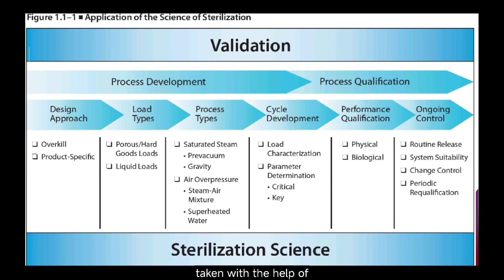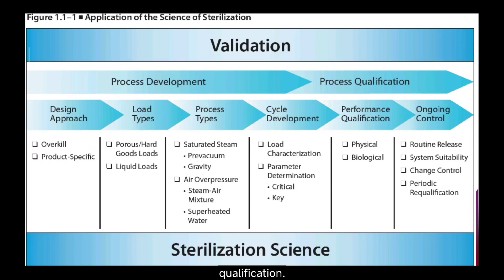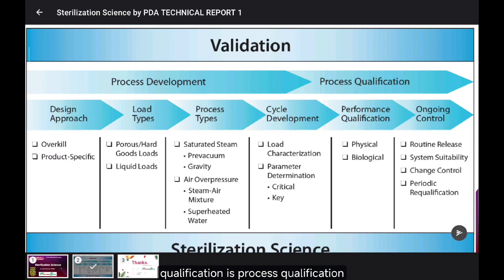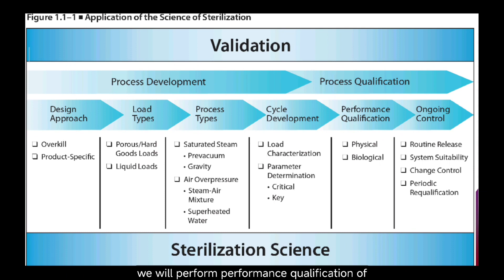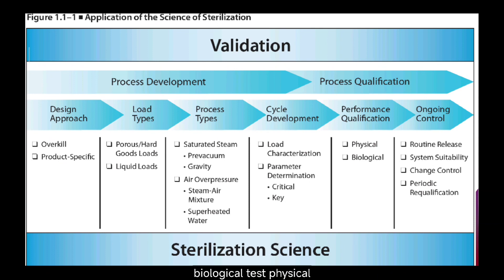After cycle development, final performance qualification runs are taken with the help of physical or external thermocouples and biological indicators. The second phase is process qualification, in which we perform performance qualification of the developed cycle and load. Performance qualification involves physical and biological tests — physical includes thermocouples and temperature mapping studies, along with biological challenge tests.